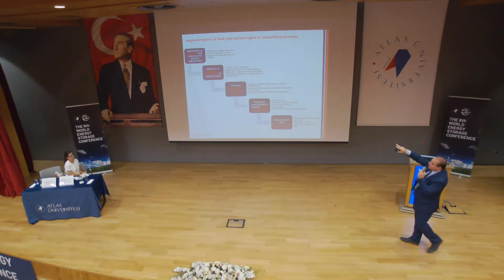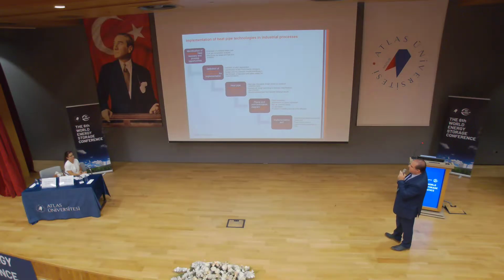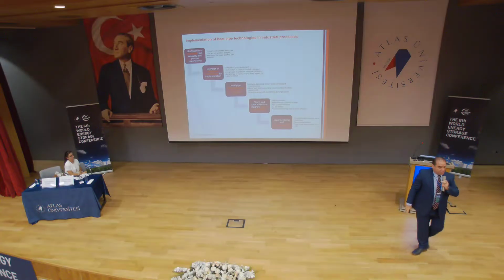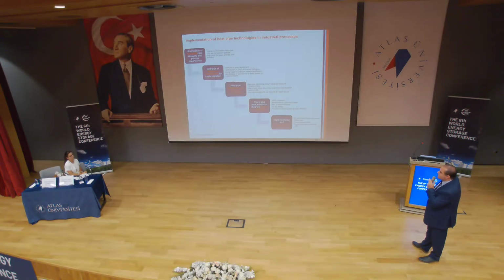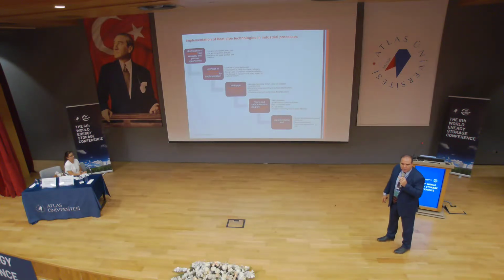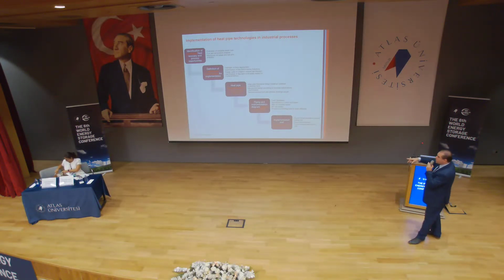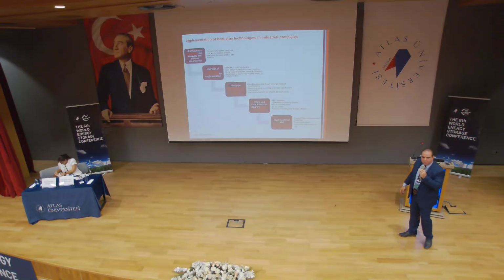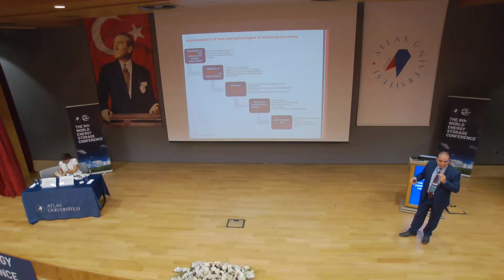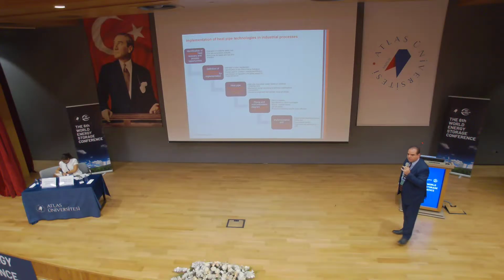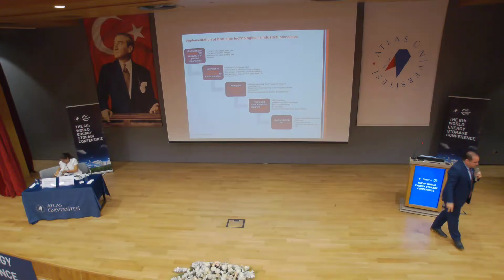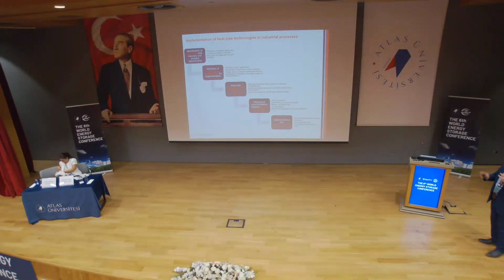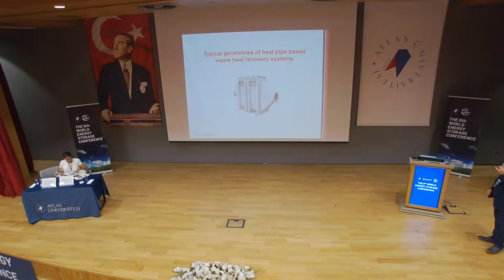Once we understand the streams and their composition, we identify the technical specifications required. Because I'm working with heat pipe systems, these scenarios require heat pipe systems, I look at the system, design it theoretically, run the mechanical design by the company that will manufacture it. If there are any issues, if all is good, we then go to the piping and instrumentation diagram with the site, making sure all the sensors and control strategy are in place. After that we work on implementation and commissioning. It's a long process, but if you do it right, everything goes without a hitch.